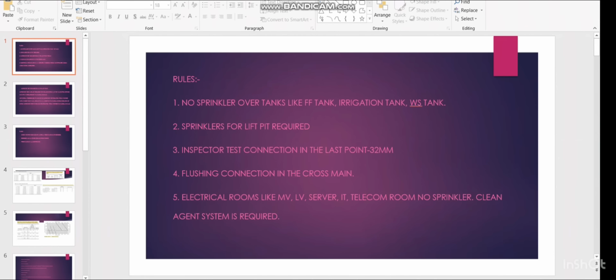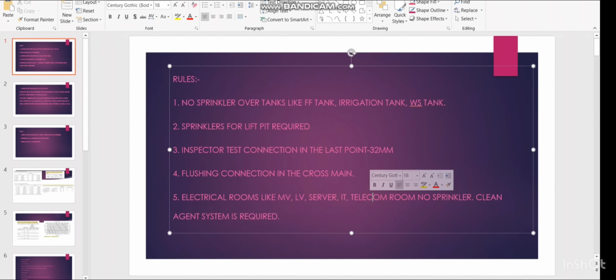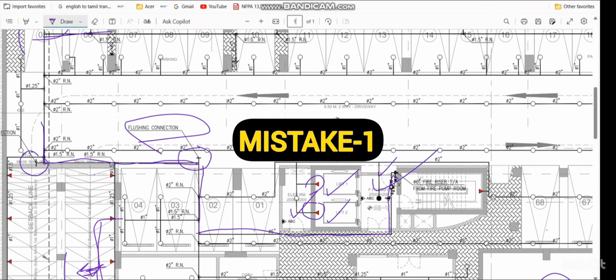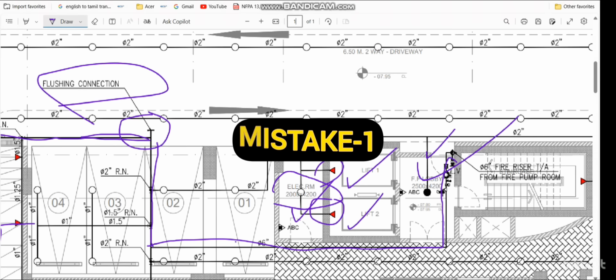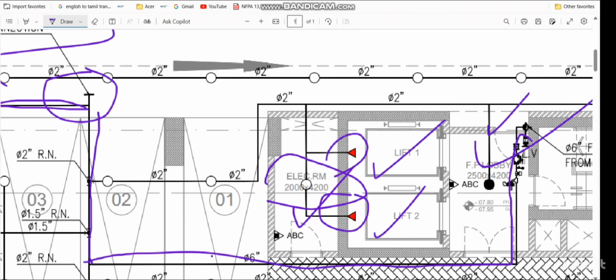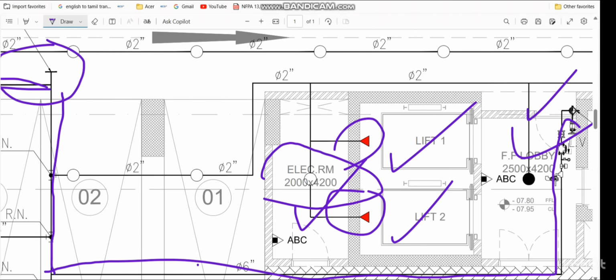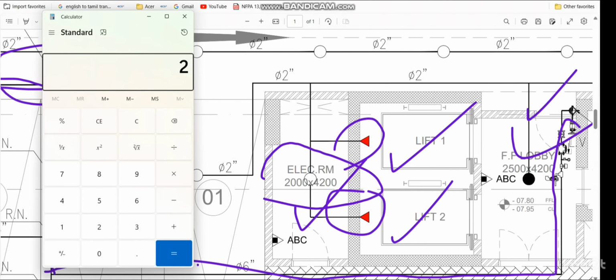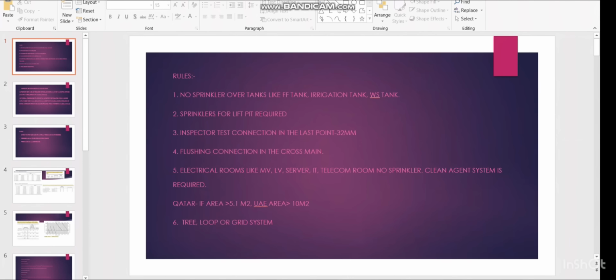So the next rule is electrical rooms like MV room, LV room, server room, IT room, telecom room: no sprinkler, clean agent system should be provided. So we have some special requirement. Let's see that. So you can see this electrical room. The area here is 2000 by 4200. So the total area for this room, I will tell the answer in meter: 2 meter into 4.2, it is 8.4 meter square.